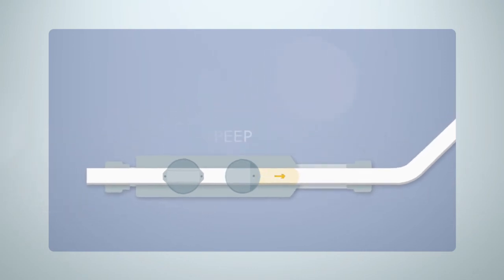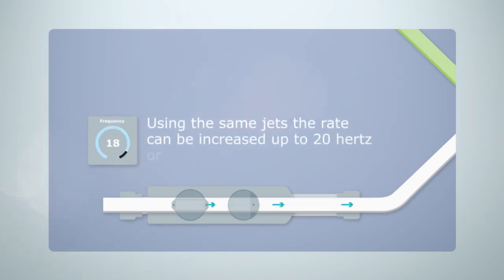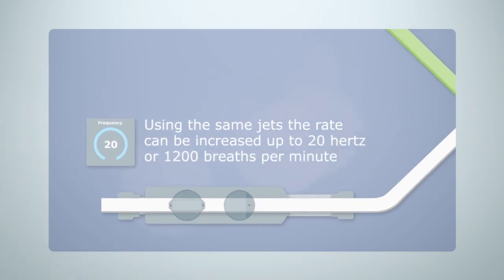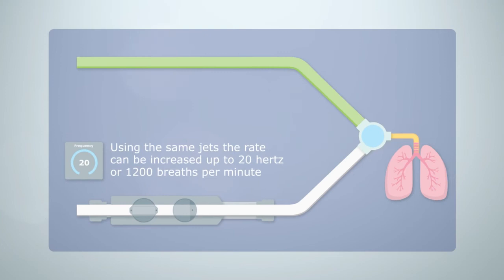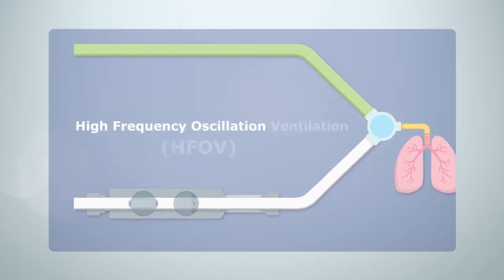Unlike a mechanical valve, air has no significant inertia or delay. Therefore using the same jets the rate can be increased easily up to 20 hertz or 1200 breaths per minute whilst managing the flow and pressure with immense precision. This enables the SLE 6000 to give high frequency oscillation ventilation.